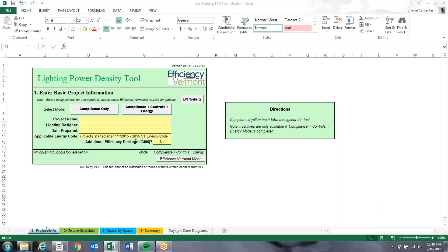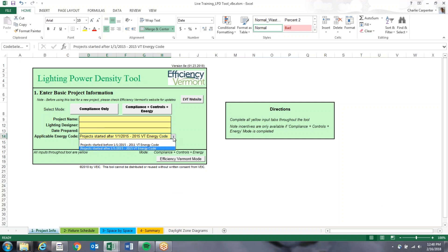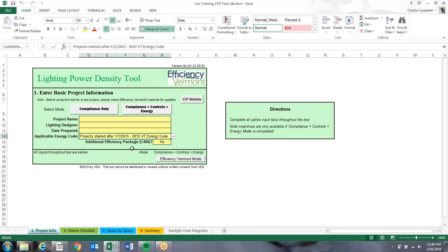Getting started with this tool, we'll start on the first tab, the Project Info tab. This is where you put in the project name, your name, the date you've prepared it, and the applicable code, which is the 2015 energy code. The default mode should be the Compliance, Controls, and Energy function — that's what you need to do to get incentives for this tool. There's an additional efficiency package, C406 — leave that as no, unless the project is required by code to have an additional 10% lighting power density reduction.